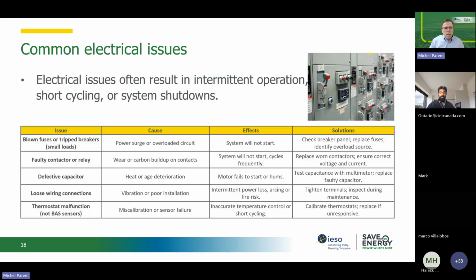The last line there says thermostat malfunction. That is actually not that common in most commercial buildings because we don't actually use a lot of thermostats. In the smaller buildings that have rooftop units, you do have thermostats. Most of the medium to large size buildings have not thermostats, but BAS sensors. That's a whole different problem. When we have BAS sensors, it is not a thermostat. But if you have a thermostat malfunction, even though the table says it could be miscalibration or sensor failure, it's usually failure.